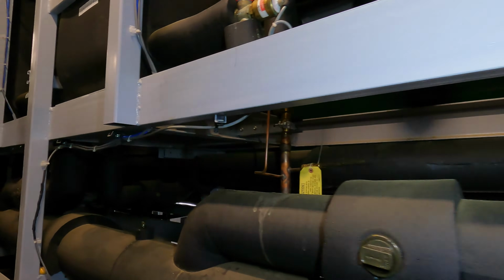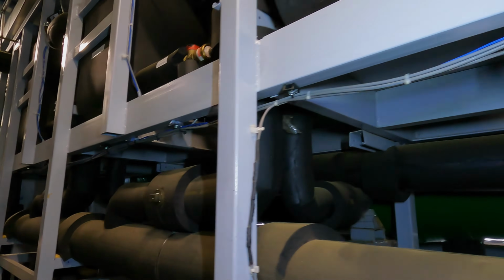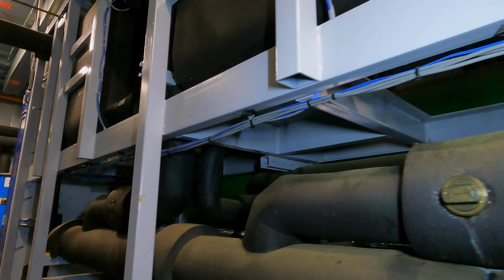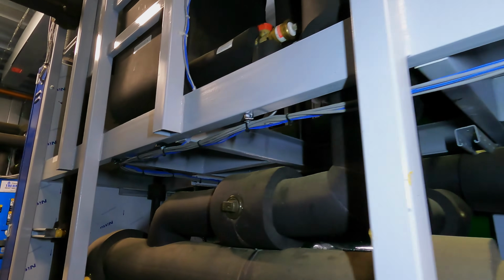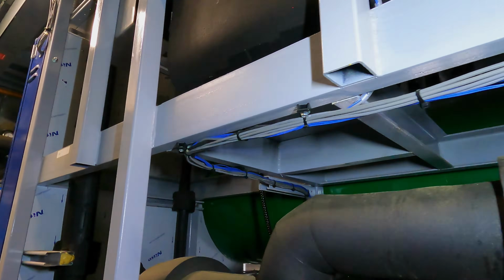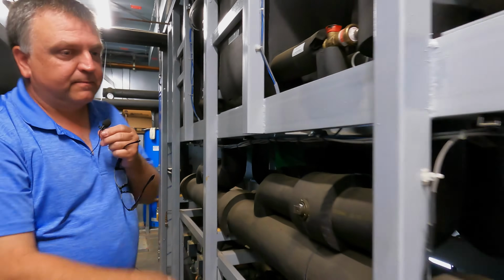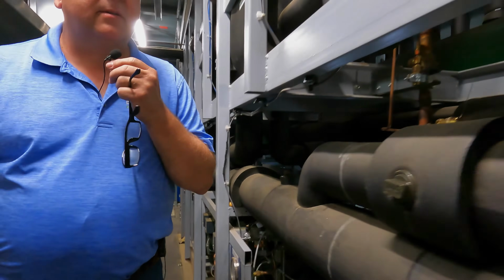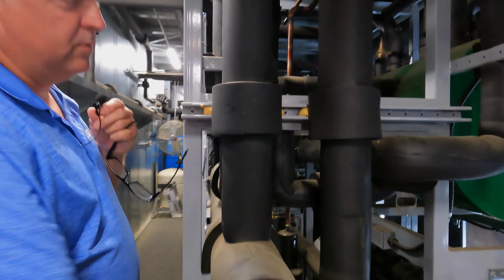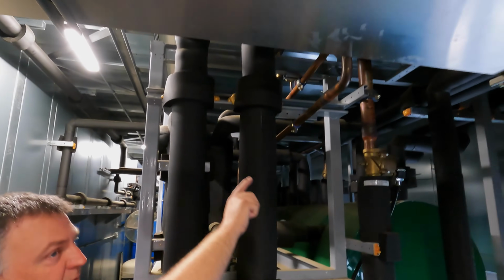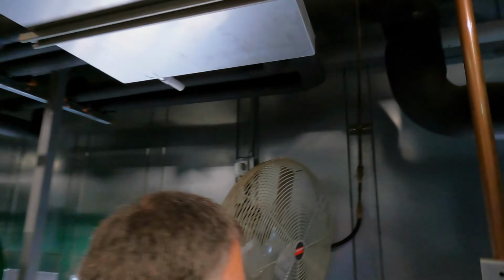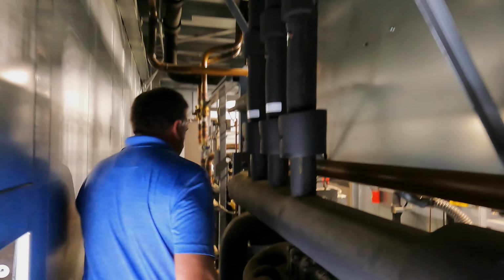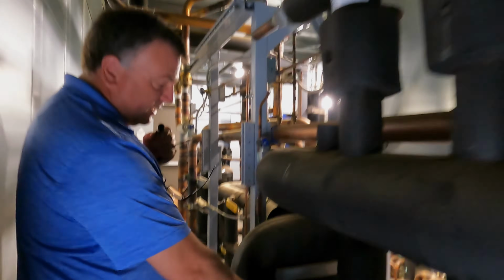It's insulated because it gets cold. You can see it'll sweat a little bit. We have 3 condenser evaporators, so we have 3 headers coming into it. This is our suction vapor coming out. It's piped into here, comes over here, comes into our suction header. A lot of piping, isn't it, guys? And it comes to this big vessel.